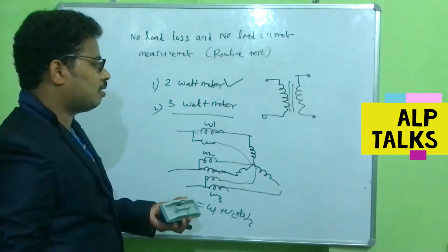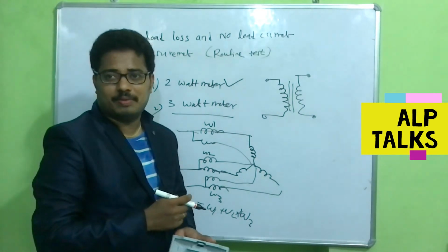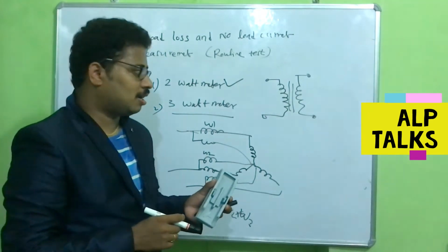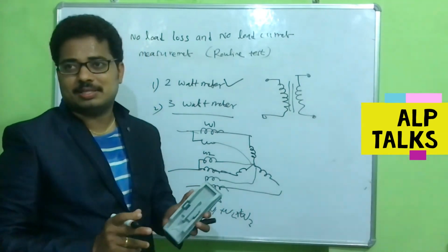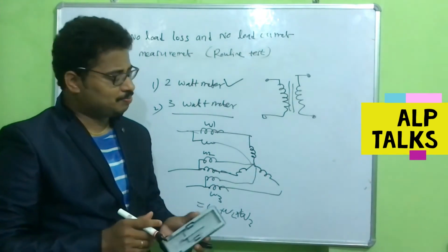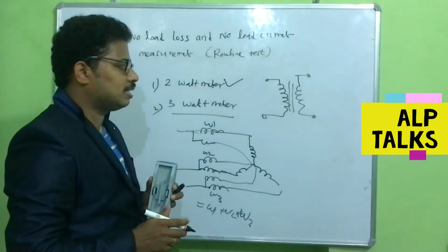So this is summation of all the 3 readings. This is the best method, we can say. Most of the times we should prefer this method, because even though little bit variations are there in the supply voltage and voltage unbalances, this method will give still a good result.